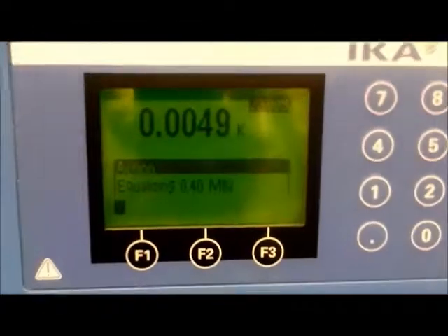And then once that is done and it is stabilized for a minute or so, it will actually do the firing on its own. You're not required to do anything. All automated, and after about 8 minutes, it'll then give you the results on the screen. 8 minutes later, we get the results, and the result will just be a temperature or an energy? The result will be an energy per gram. So it won't even let us get the temperature? If we wanted to, we could sit here and record the temperature, but this machine will not provide you with a temperature. All right, and it'll give us the energy per gram? Per gram. Of what we put in there? Exactly. Okay.